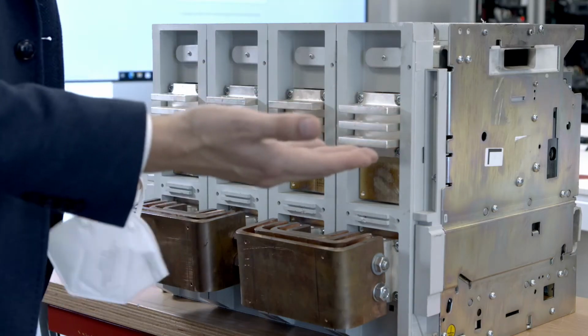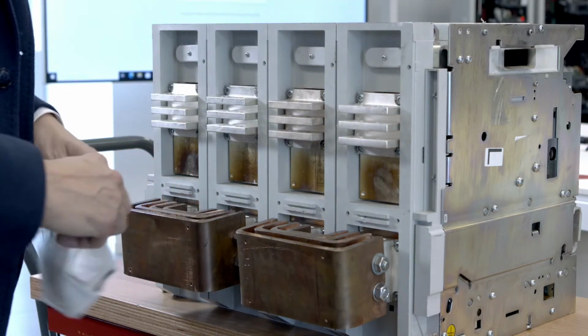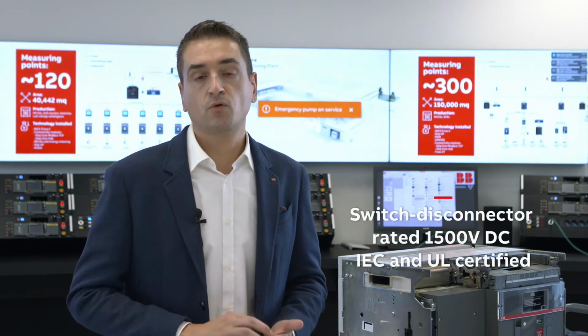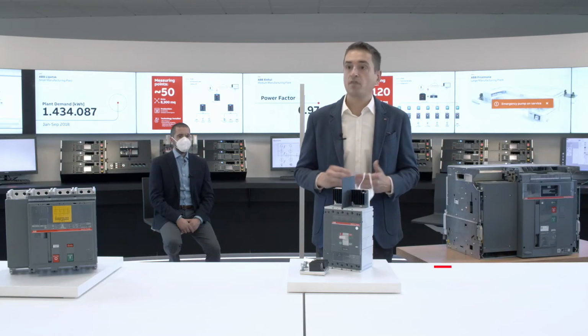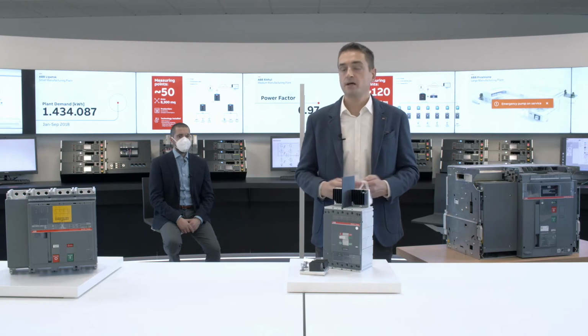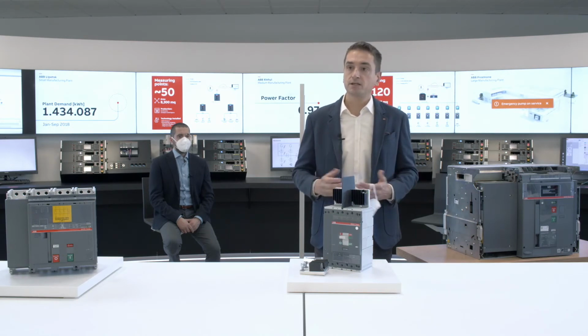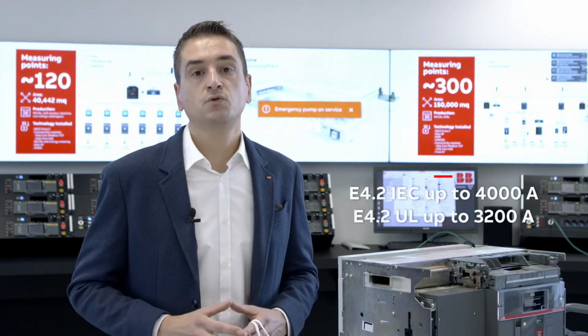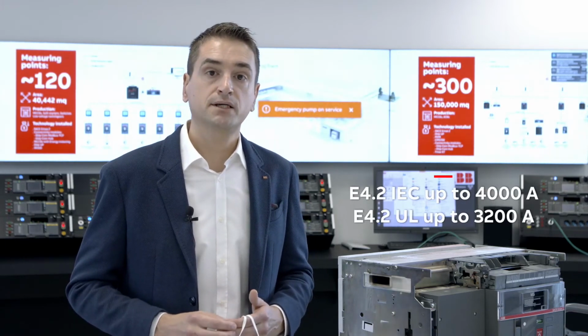This is our new switch disconnector E4.2 MS DC. This is based on Emax2 air circuit breaker, and we developed it with the target of 1500 volt DC, with specific solution for DC applications. Our new switch disconnectors cover both IEC and UL standards. For IEC, we have the utilization category PV2, meaning that it's the most demanding utilization category for IEC. For UL, we have both UL 489B and UL 489F, so we cover photovoltaic application and energy storage solutions. Nominal currents are up to 4,000 amps IEC and 3,200 amps UL.